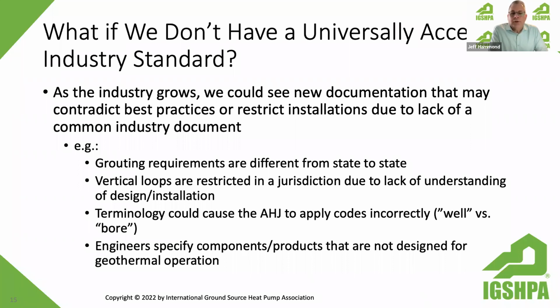We've seen this with the term well or bore. A closed coupled ground source system uses bores. An open loop system or groundwater system uses wells. It sounds like semantics, but if you're looking at local code and there's a code for water wells, you really don't want that code to necessarily apply to ground loops. It might actually cause problems with the installing contractor and the driller because of the simple terminology of well versus bore. So it's really important that we have a standard and a set of definitions so that we're not causing confusion out there.